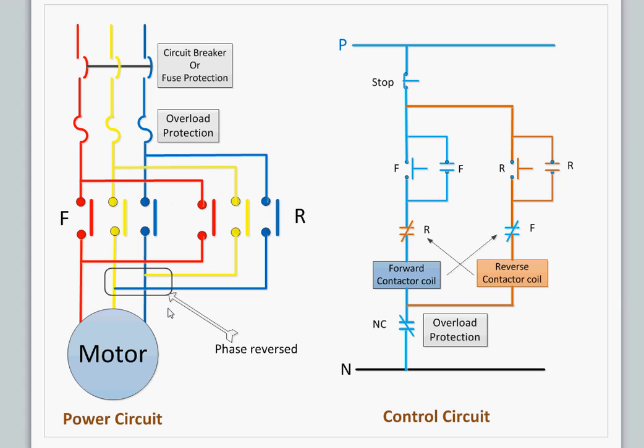The direction is changed when you swap the phases. You can see here the yellow phase in the forward side when the forward contactor operates goes here. But during reverse, the yellow phase is applied to the blue side and the blue phase to the yellow side. That's the key to changing the motor's direction.